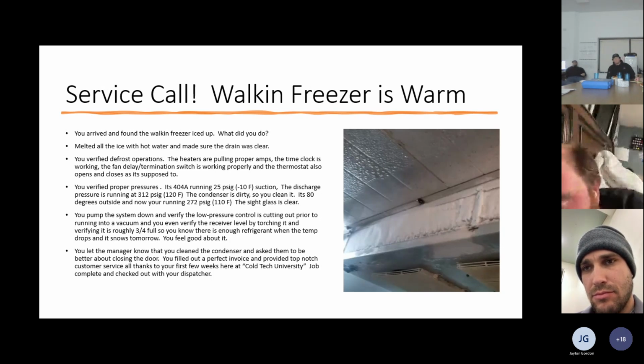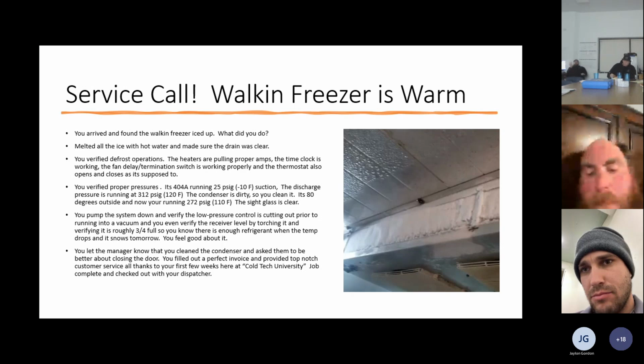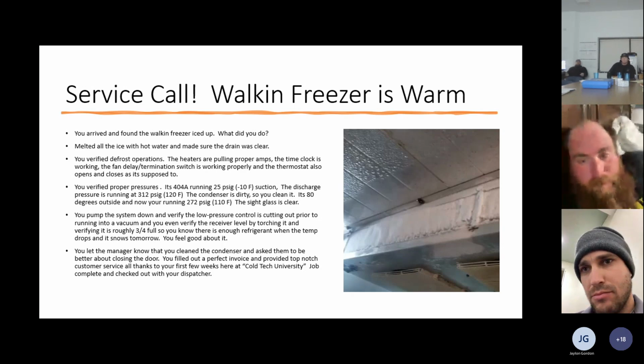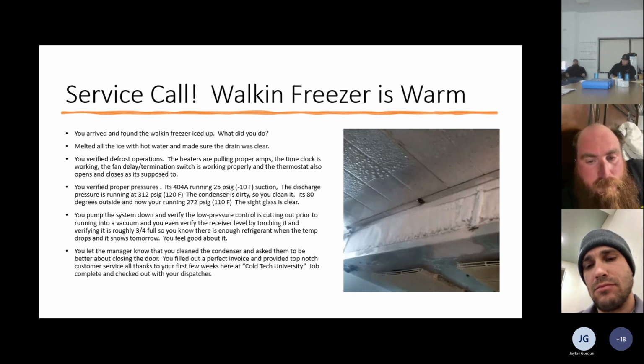And most supermarkets will have an actual gauge so you know your receiver level. It will fluctuate a little bit, especially if the split valve's not working or the fans aren't programmed right. But in this specific example, say you're working on a walk-in freezer at Applebee's with a single system with a small receiver on the unit. Things that are more critically charged, those ambient conditions are going to really affect the system. All those new units that they make with 2 fans run constantly with no fan cycle switches. They sit there and run fans nonstop in the wintertime.